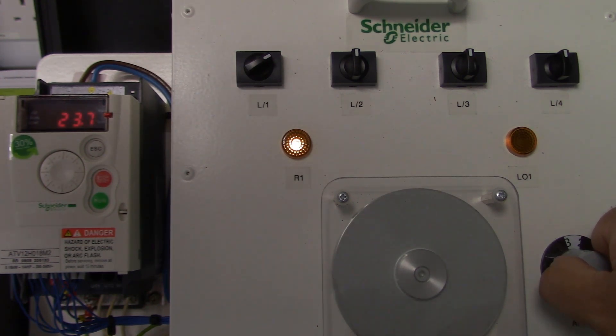With this drive if you only need one set point then use the PII and rPI parameters. PII switches on the internal set point and RPI is the reference set point inside the drive. This would override the reference in FR1 parameter.